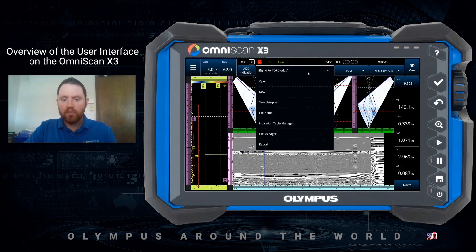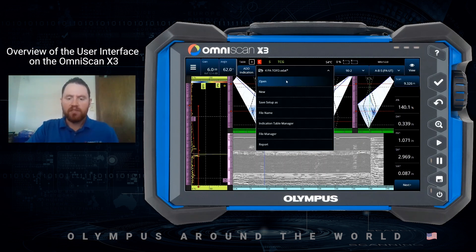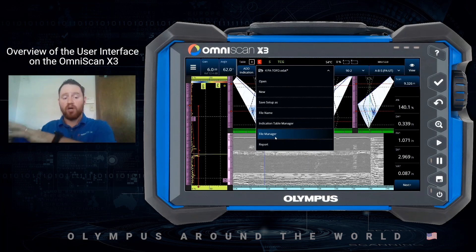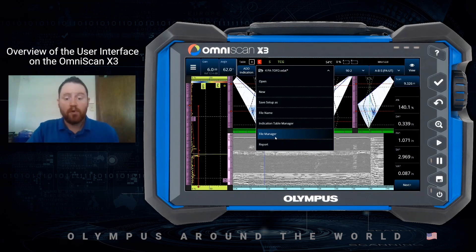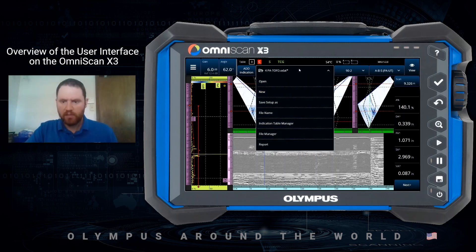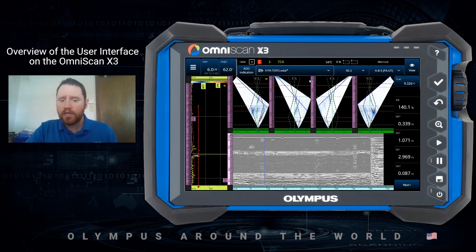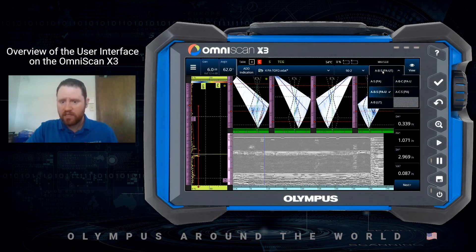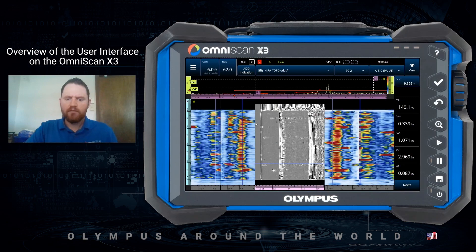In the middle, we have our dropdown box for navigating through all of your files and file management. With this dropdown, we can see how to open a file, start a new file from scratch, preset the file name for your data files, the file manager for pulling files on and off the instrument, and some of our reporting functions. The next icon over is for switching from group to group — I can see all five groups active on this data file. Then the next button over controls the display layout, allowing me to switch to a different format for data collection or data analysis.